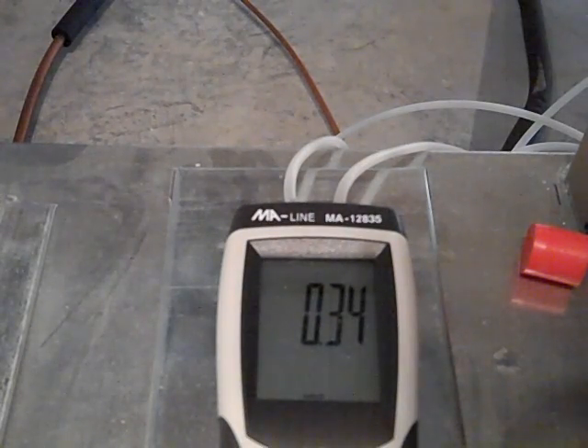I've just turned on my ERV, which dumps into this return. You can see — I'll shut it off and it'll come back up. That was just on low. I'm going to crank it up to high. This is dumping into the return so that should draw. Here it comes — so now I'm about 0.3.